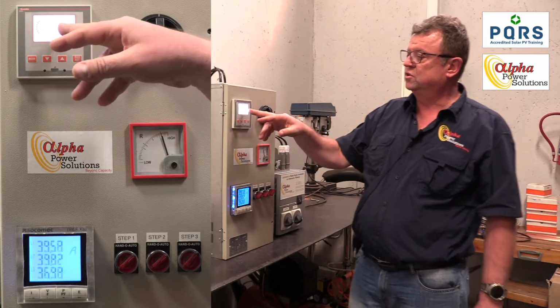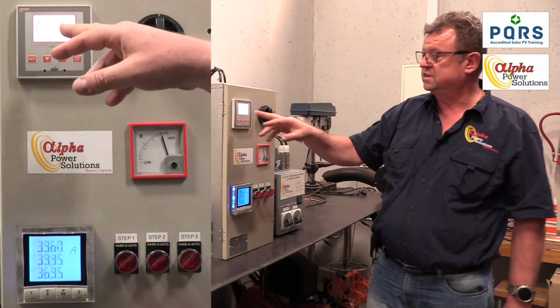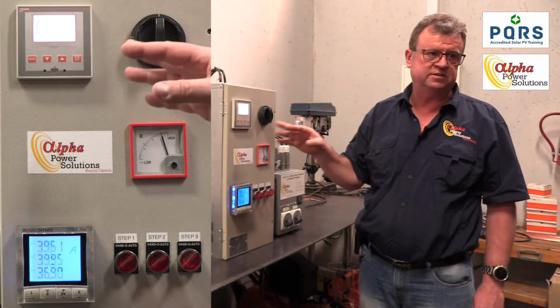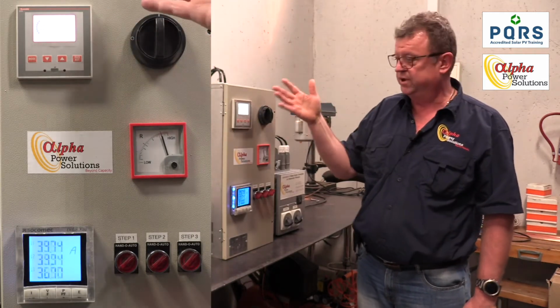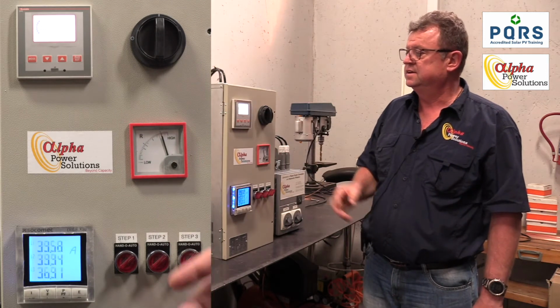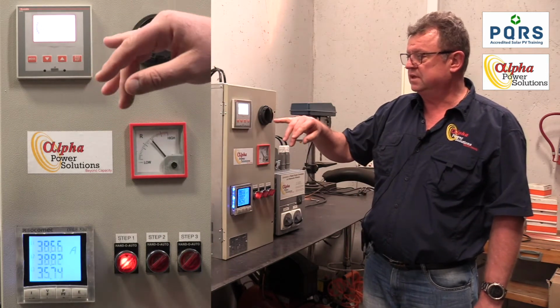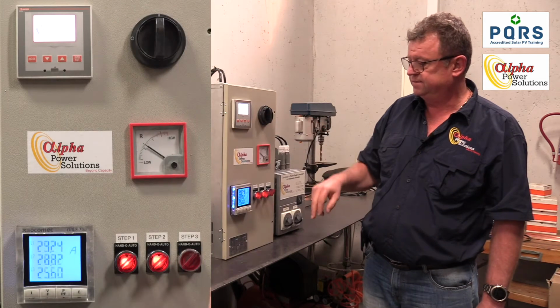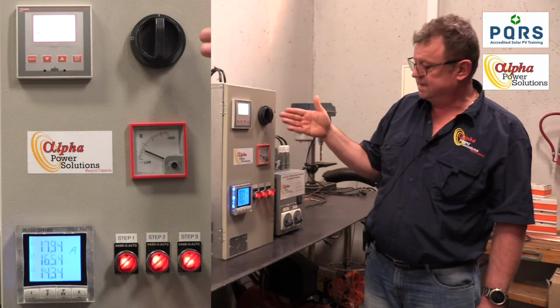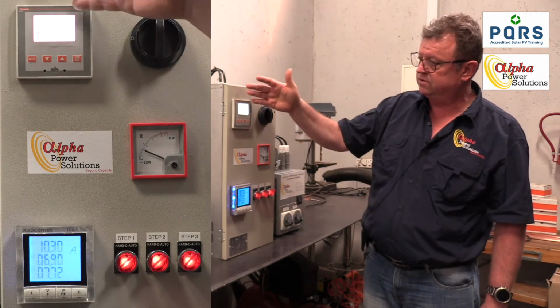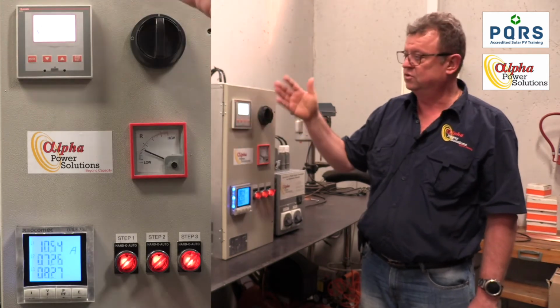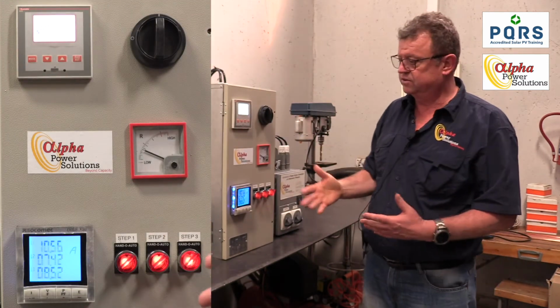So the controller now knows that it needs to do something, and it's waiting for the capacitors to discharge before bringing the steps in automatically. So there's this first step coming in, the second and the third. So now this device had control of the power factor correction.